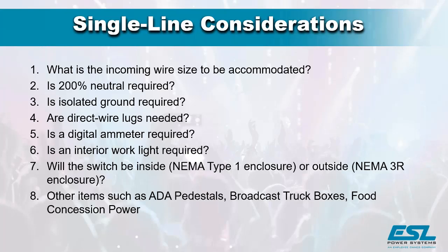We like to see exactly how many conduits and what size they'll be. Is 200% neutral, double neutral, required? Is an isolated ground required? Are direct wire lugs needed? That may or may not be on the single line, might be in the specifications. Is a digital ammeter required? Once again, probably in the specs more likely, and the interior work light, the same thing, all those options we described earlier.